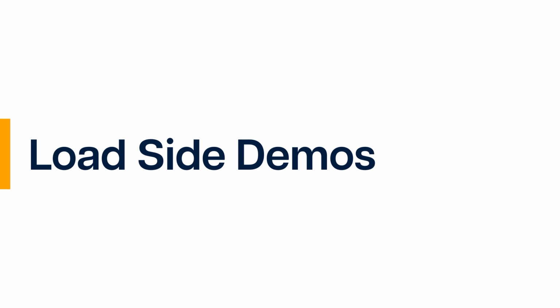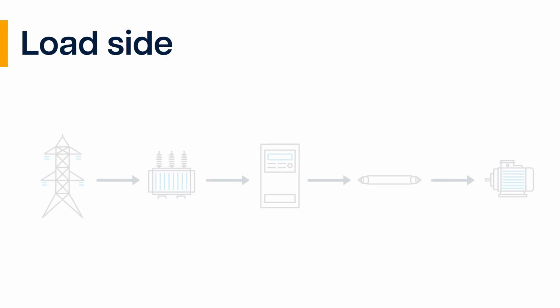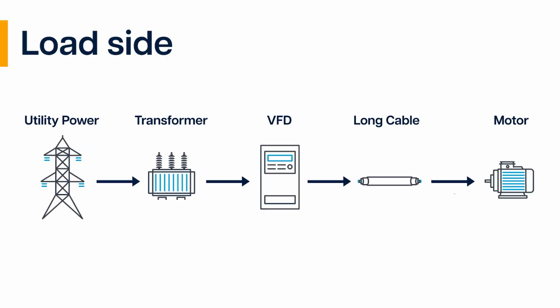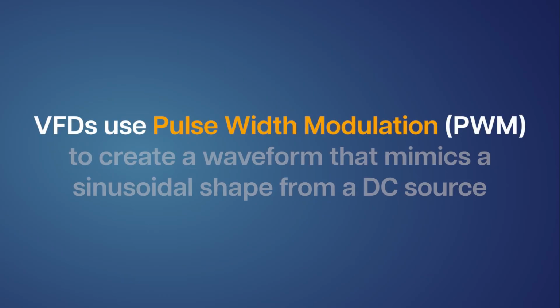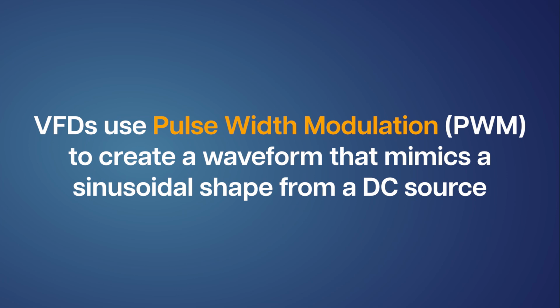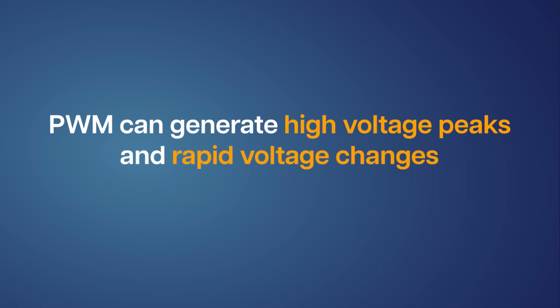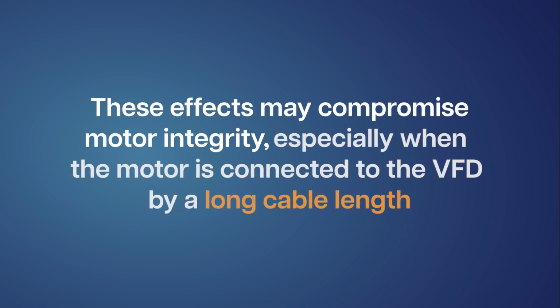We're transitioning to demonstrations focused on the solutions for the load side. The VFD adjusts motor speed by altering the frequency of the power supplied. It uses pulse width modulation to create a waveform that mimics a sinusoidal shape from a direct current source. Although PWM is effective for speed control, it can generate high voltage peaks and rapid voltage changes, known as dV/dt. These may compromise the motor's integrity, especially when the motor is connected by a long cable length to the VFD.